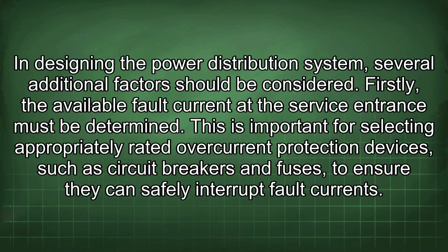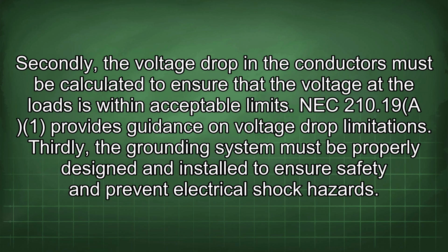Firstly, the available fault current at the service entrance must be determined. This is important for selecting appropriately rated overcurrent protection devices, such as circuit breakers and fuses, to ensure they can safely interrupt fault currents. Secondly, the voltage drop in the conductors must be calculated to ensure that the voltage at the loads is within acceptable limits. NEC 210.19(A)(1) provides guidance on voltage drop limitations.